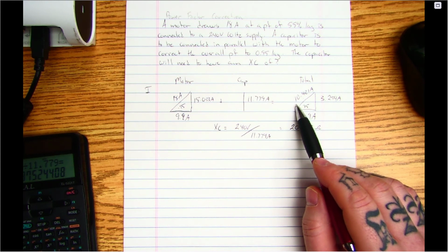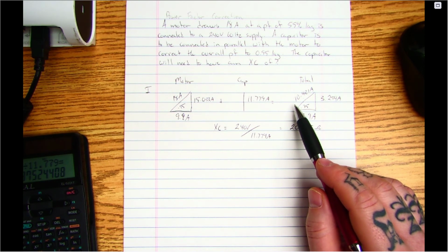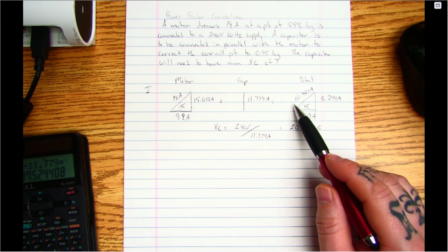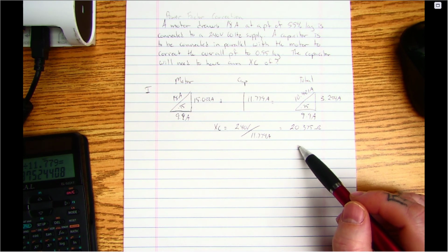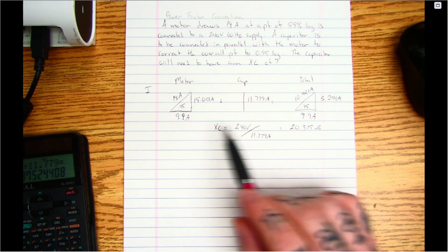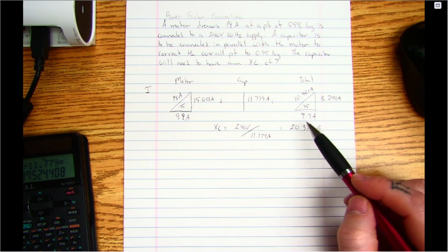If we reduce the line current, we can reduce the size of the conductors, we can have more room on our supply transformers for more supply. Again, these are small currents, but these could be up to hundreds of amps on a service. Okay, so that's kind of the whole point of power factor correction. Take a very poor power factor piece of equipment, or even a whole plant or a whole shop, and then add a capacitor bank to correct it and reduce our line current coming in.